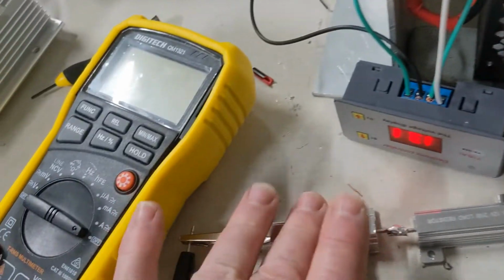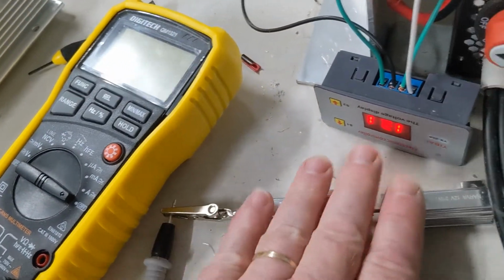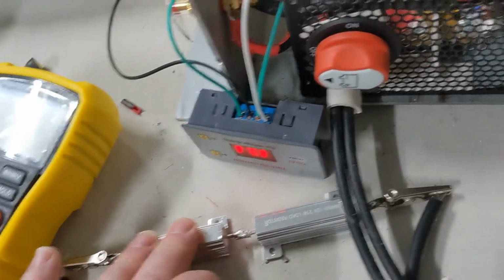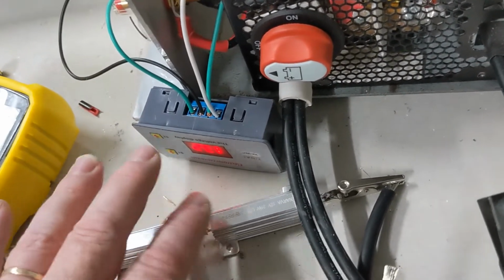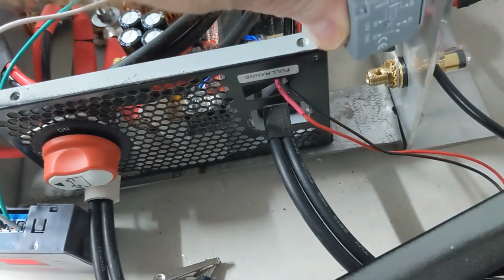One more thing we might do before we close off is check for heat. The resistors are reasonable, we're only pumping 100 watts on them, so it shouldn't be too hot. The relay was an issue before. It's warmish, but it feels like on the coil side, not the load side. The load side is here, and the coils are on this side.